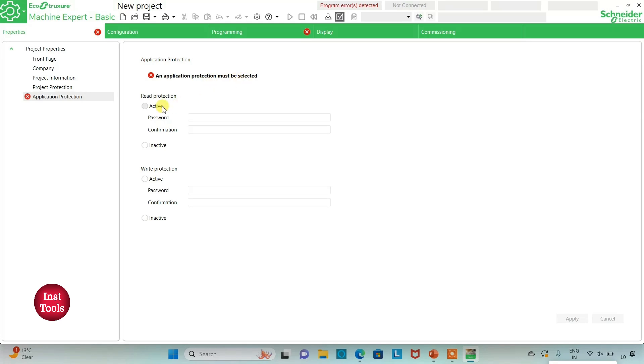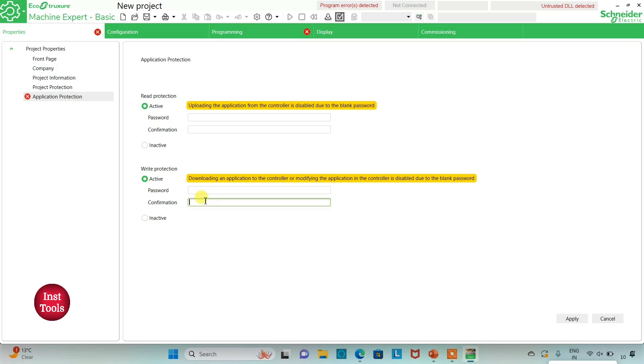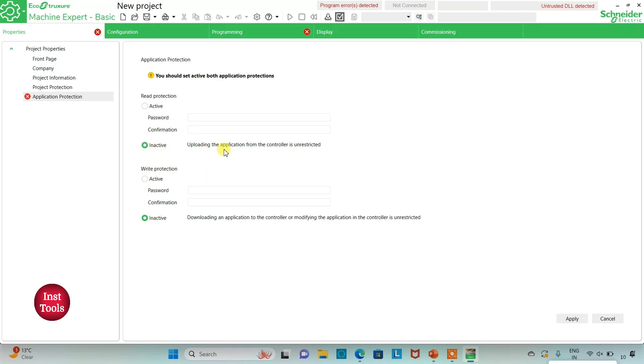An application protection must be selected. If we keep read protection as active, we have to set a password and confirmation. If we keep write protection as inactive, uploading the application from the controller is unrestricted and downloading or modifying the application in the controller is unrestricted. If write protection is active, downloading and modifying the application will be restricted — it will ask for a password. For now we will keep these inactive and click on Apply.